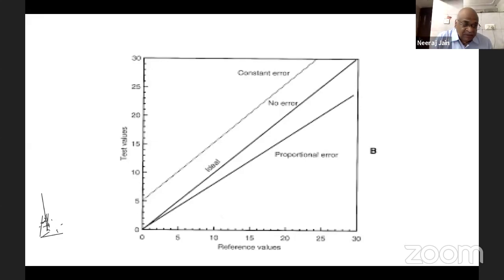But it is very difficult to get the ideal situation. But if it more or less overlaps this line, that means it is providing more or less the same performance. But suppose there is a line which is above this ideal line and it starts at 5, that means there is an intercept. If the line is parallel to this ideal situation, that means you are continuously getting values higher than expected, and the difference is the same at all levels. This is called systematic constant error.